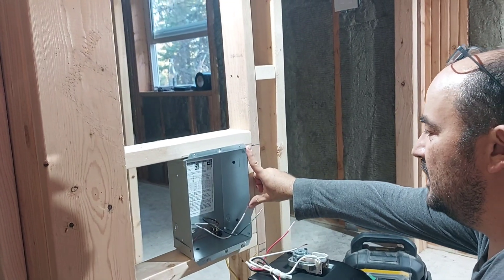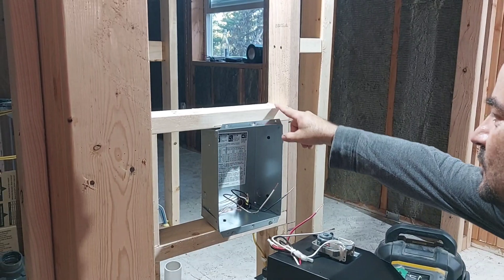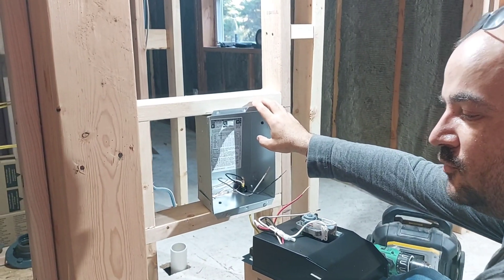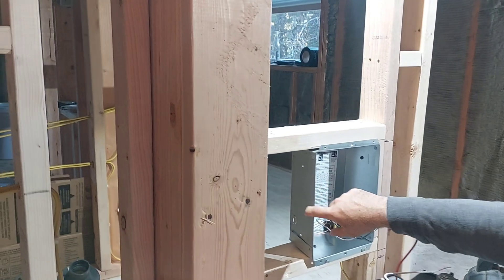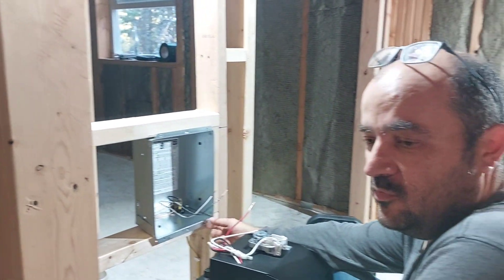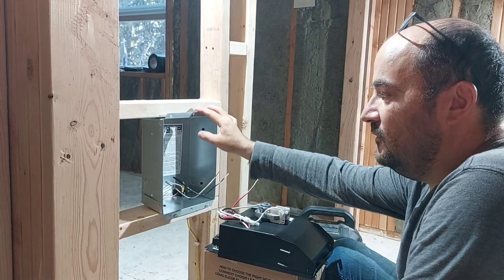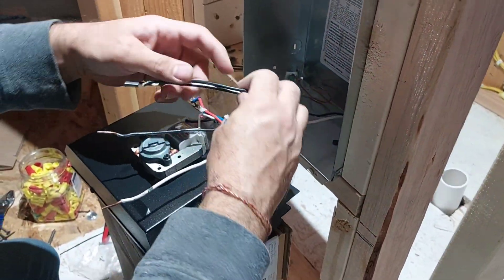This is the way I did it — I did the frame. The height of this metal box is 10 inches, so I put it at 10 inches. To make my life easier, I know that the drywall will be 5/8 inch, so I make a mark on the box where the 5/8 is. That way I don't have to remove the box again — I install it, then I bring the drywall and everything will fit perfectly. It's very easy.